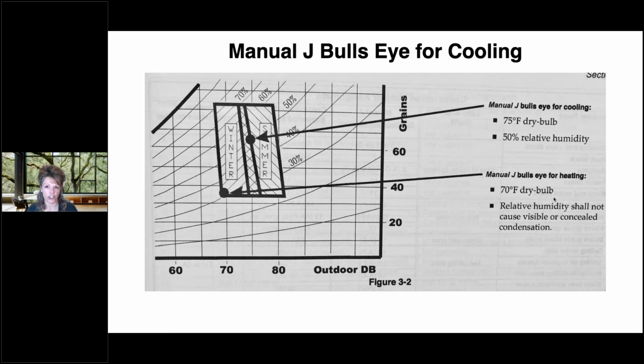So our manual J bullseye for cooling for designing is 75 degrees and 50% relative humidity. So when we're designing the AC system, we're designing for peak loads for 75 degrees and 50% relative humidity. The reality is when we're designing these systems that they're going to run at 1% of the time at that peak load condition. So the challenging part is how do we control that relative humidity or that latent load when the AC is not running.